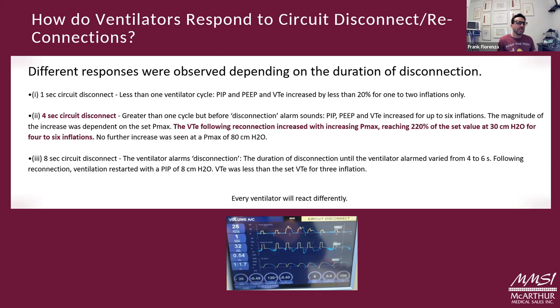So what happens is you disconnect a circuit, all the pressures in the lungs drop to zero, everything drops to zero. Then at that point they're reconnected to the ventilator. The ventilator overshoots trying to figure out where the settings were and find the magic numbers. Then it claws back and gets back to its homeostasis or steady state. But at that time you had complete collapse and then 6 breaths of varying parameters.